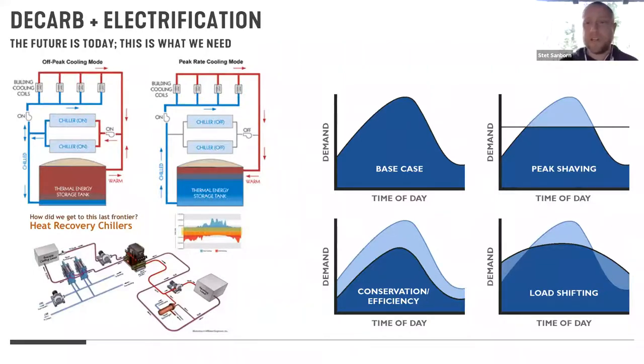And by pushing load earlier in the day, we have lower outside air temperatures. Our chiller and cooling tower are doing more efficient work, and we store that chilled water so I can just turn everything off except my pumps from 4 to 9 p.m. as I run into my peak load. That's a huge driver. And because of those demand charges that are happening in the afternoon, it's making the financial case for thermal energy storage, I mean, it was already cost effective, but now it's just a no-brainer on our projects, especially at scale.